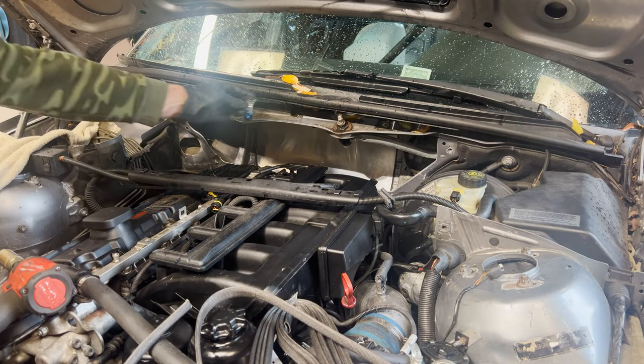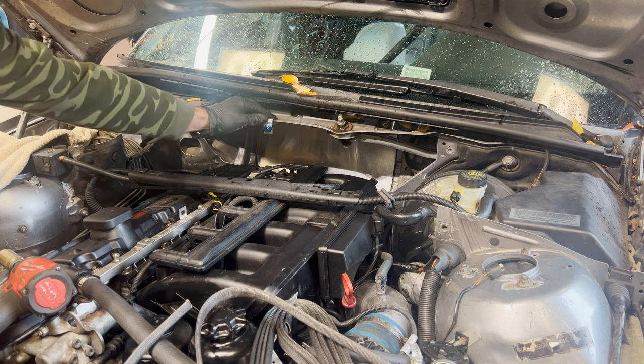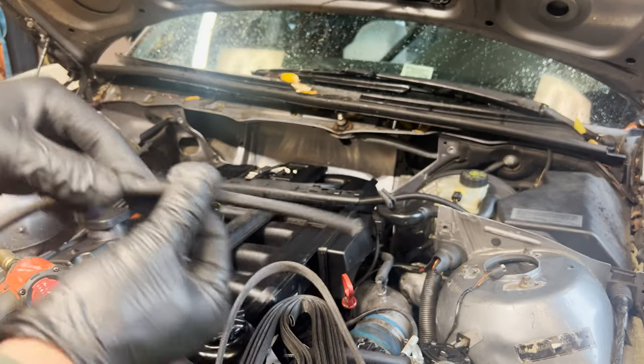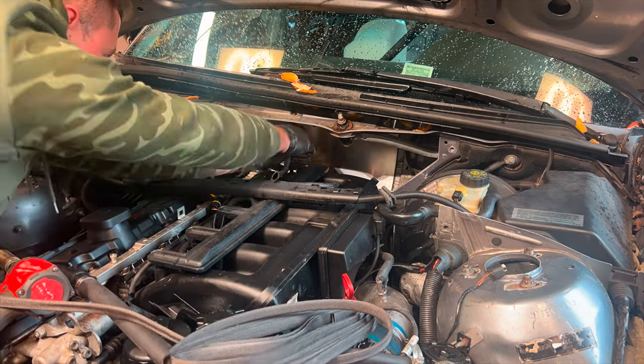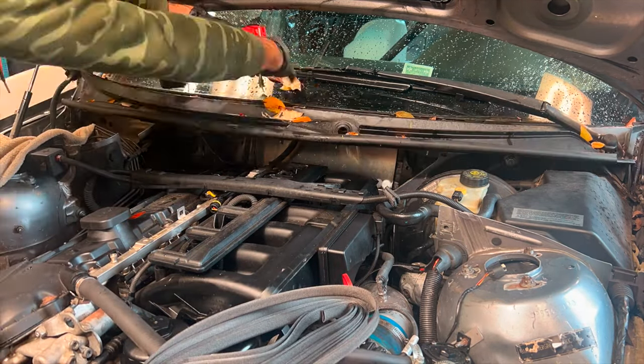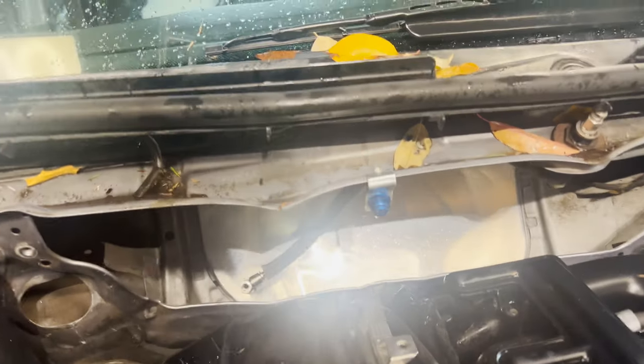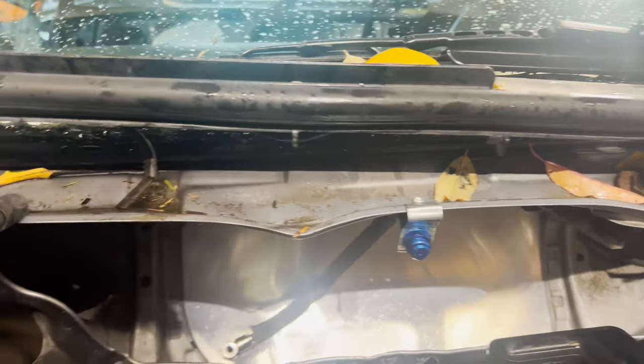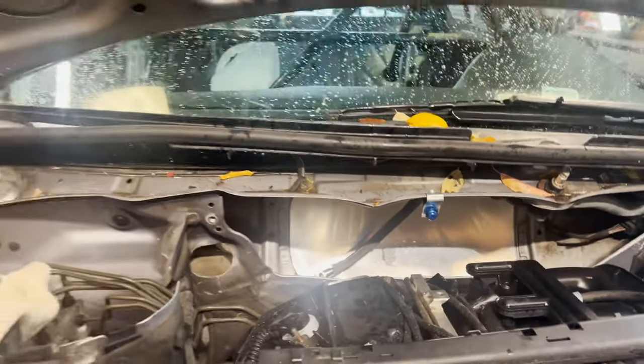I moved the cowl up and we can point the nozzle in the direction we desire. Before placing it, I applied the fire jacket that's provided for the tubing — cut the tube to length and mounted it right there. Here's a close-up of the first nozzle: very simple, just use a self-tapping screw to tap it into the sheet metal of the chassis, with the fire-retardant jacket in place.